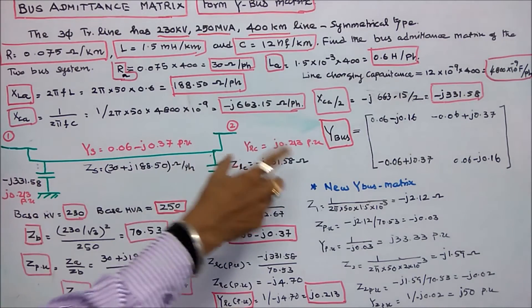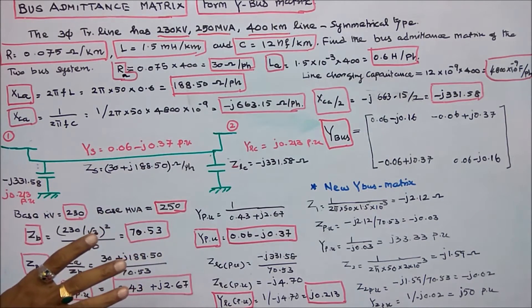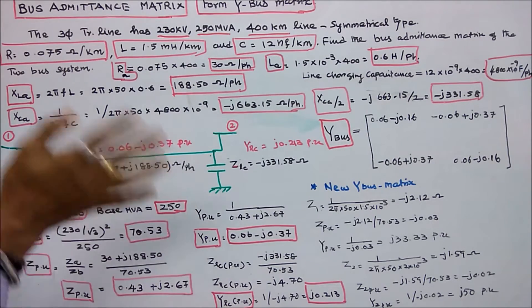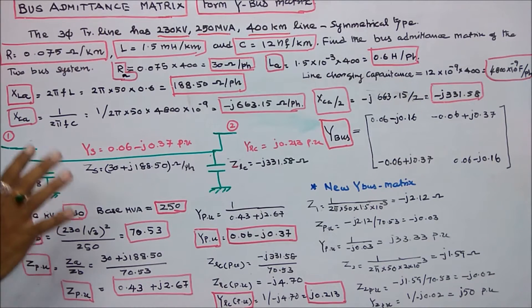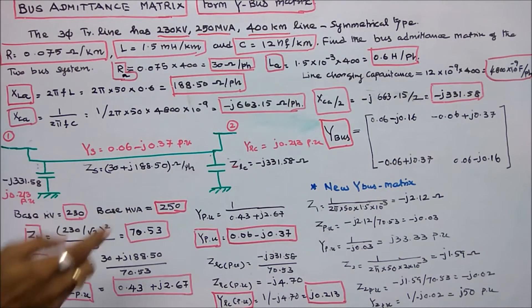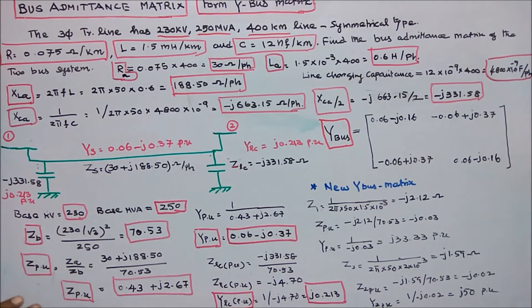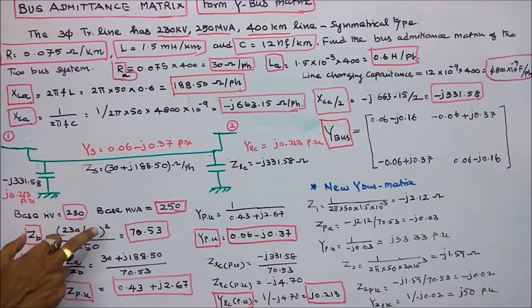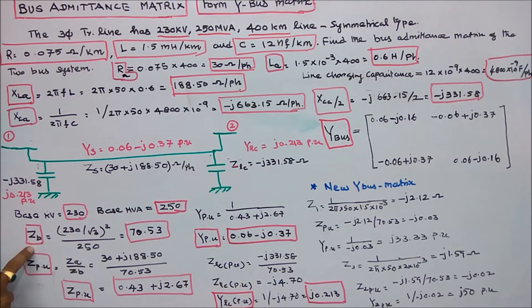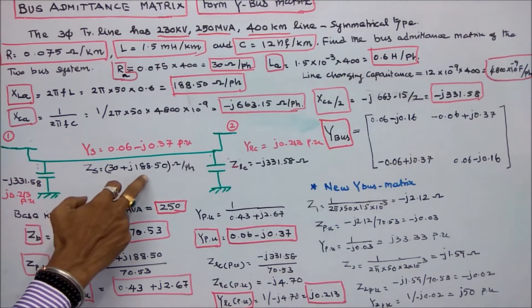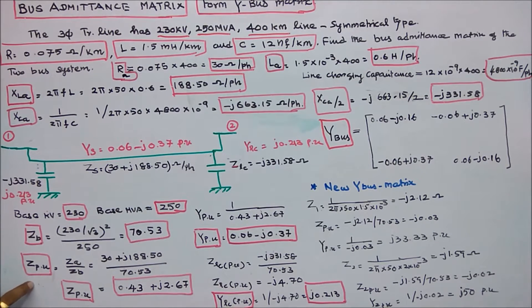All values are in ohms per phase, so I need to convert them into per unit. I choose base kV = 230 kV (line-to-line), so phase voltage is 230/√3. Base MVA = 250. Base impedance = (230/√3)² / 250 = 70.53 ohms. Actual series impedance is 30 + j188.50, so per unit impedance Z_pu = actual / base = 0.43 + j2.67 per unit.